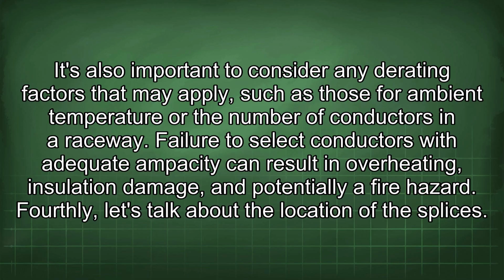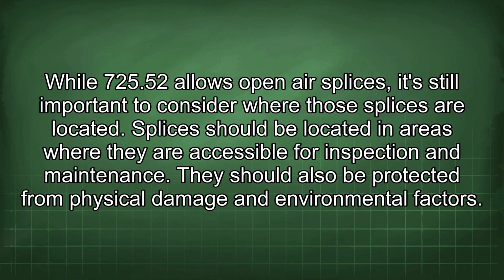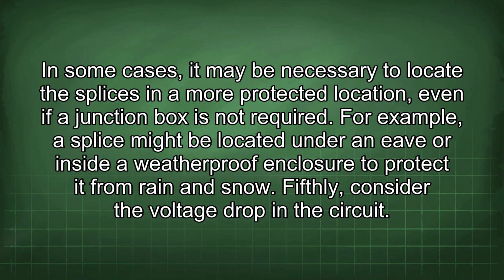Fourthly, let's talk about the location of the splices. While 725.52 allows open-air splices, it's still important to consider where those splices are located. Splices should be located in areas where they are accessible for inspection and maintenance. They should also be protected from physical damage and environmental factors. In some cases, it may be necessary to locate the splices in a more protected location, even if a junction box is not required. For example, a splice might be located under an eave or inside a weatherproof enclosure to protect it from rain and snow.